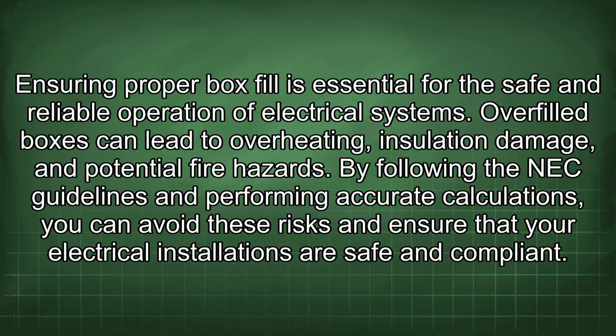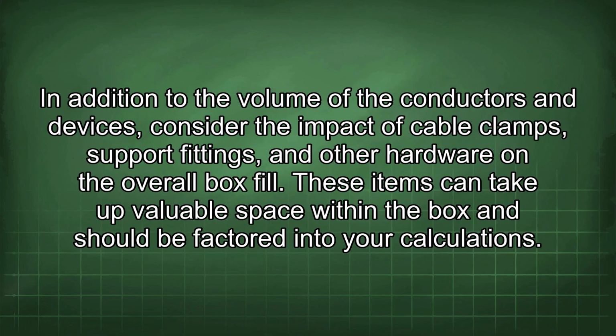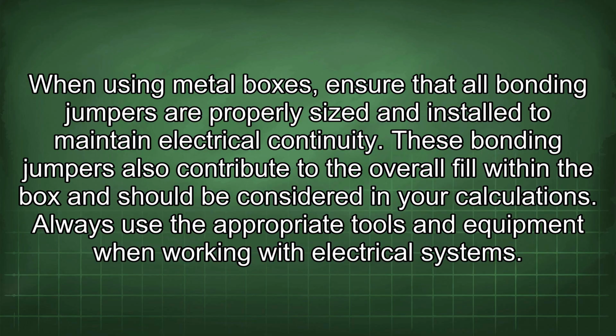In addition to the volume of the conductors and devices, consider the impact of cable clamps, support fittings, and other hardware on the overall box fill. These items can take up valuable space within the box and should be factored into your calculations. When using metal boxes, ensure that all bonding jumpers are properly sized and installed to maintain electrical continuity. These bonding jumpers also contribute to the overall fill within the box and should be considered in your calculations.